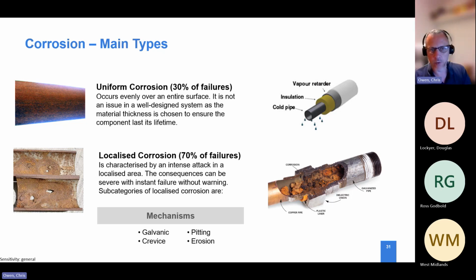And again, going back to the cold form tube, that heat affected zone obviously is inside the weld seam. It's both on the top and the bottom. So again, if you've got a tube which is completely covered in water as a result of saturated insulation, then that weld seam is going to be prone to accelerated corrosion as a result of the heat affected zone and the stresses associated with it. The localized corrosion can take place due to a number of different mechanisms, which we'll talk about now in a little bit more detail.